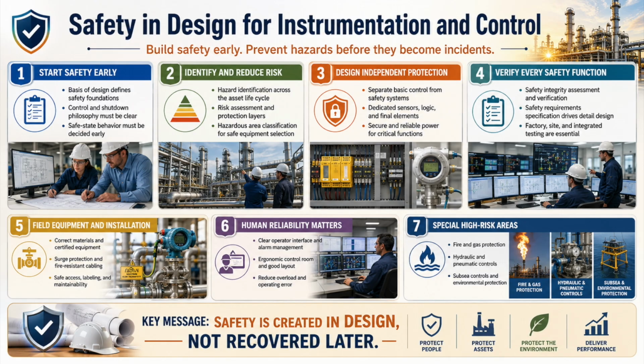It identifies which risks can be eliminated, which can be reduced through passive or mechanical protection, which require operating controls, and which require an independent instrumented safety function. This sequence matters. Do not jump immediately to sophisticated automation. Remove hazardous inventory, reduce pressure, improve containment, separate hazards, provide mechanical relief, improve layout. Only after simpler protection measures have been applied should an instrumented protection layer manage the remaining intolerable risk.